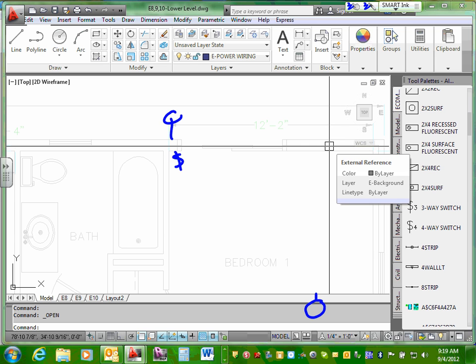All your common lights are fed from the common panel — the house panel. All lights for every apartment, outside and inside, will be fed from that apartment's panel. No more than 10 lights on one circuit — be generous, use three or four circuits. At least two to three circuits for every apartment; the common area might take one or two circuits.